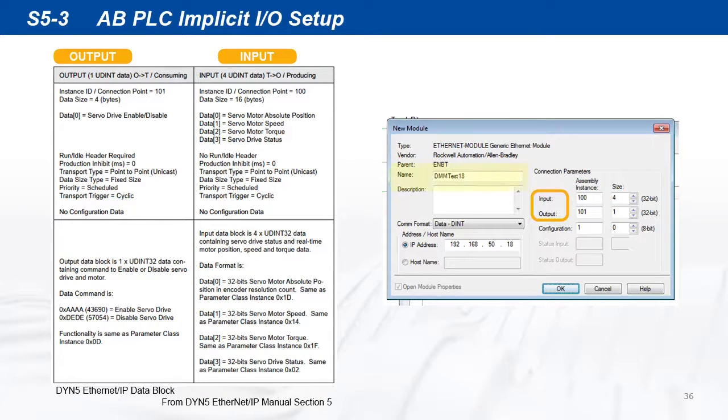Give a name to the module — in this case, we'll call the drive dmmtest18. Set the data as DINT type and set the servo drive IP address. Set input instance as 100, set to 4 blocks. Set output instance as 101, set to 1 block. Set configuration instance to 1 and 0 blocks, then click OK.